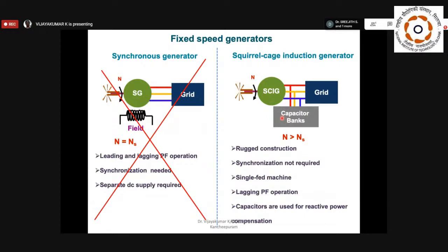But using the capacitor bank is also another disadvantage. Why? Because of selecting the capacitor values. This machine can operate from low power to full power, say 10% load to 100% load. During the low load condition, you need a capacitor bank with smaller capacitor values. If you are going with the full load condition, the capacitor bank values would be higher.